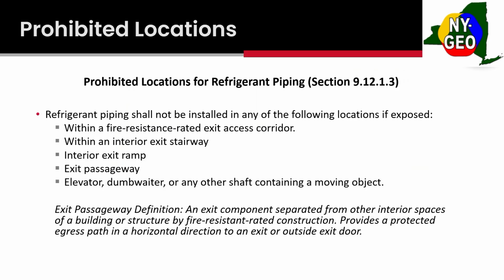So, prohibited locations for refrigerant piping. You can't install in a fire-resistant corridor, interior exit stairway, interior exit ramp, passageway, elevator, dumbwaiter, so any place where it's really an egress, an emergency escape. New in ASHRAE 15, they define the passageway. It used to be like in a school, a hallway is considered a corridor, so they have a clear rule around that: exit components separated from other interior spaces of a building or structure by fire-resistant rated construction. So keep that in mind there.